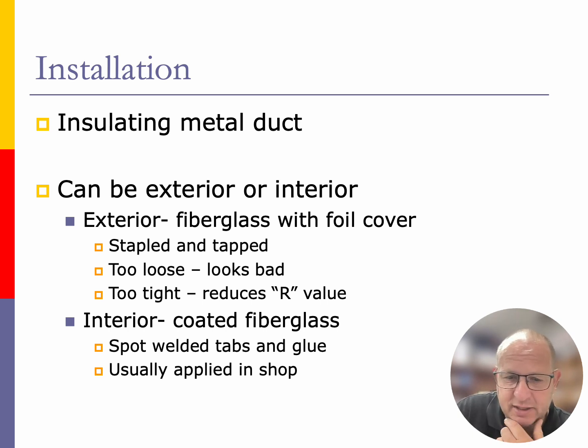When we're speaking about the insulation that goes on the interior of the pipe, if you ever have to do it, we're going to use stuff that we call tabs. These tabs have little metal clips on them that look like a nail glued to the side of the interior of the pipe, and we put the insulation over top of it. It is a special insulation that does not flake off or put particles into the air that's going to be breathed in by the customer.